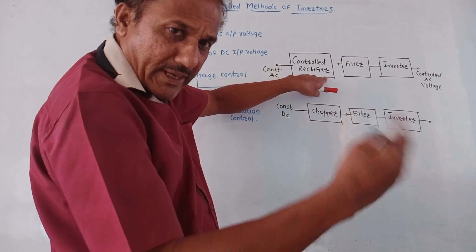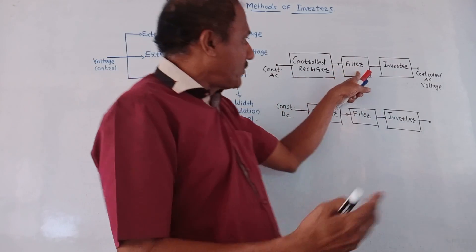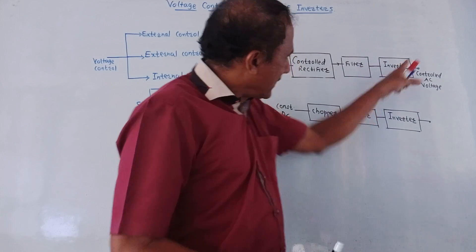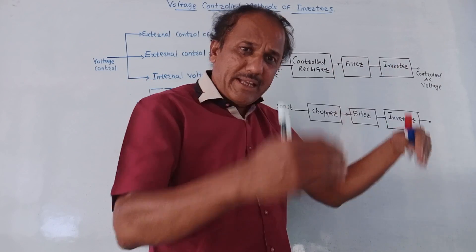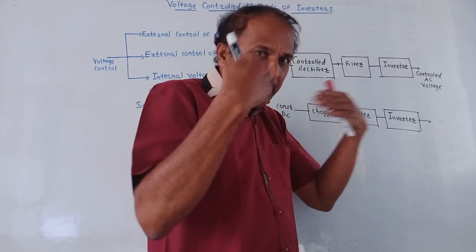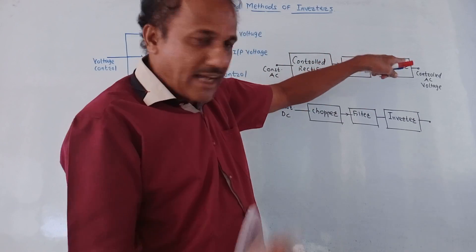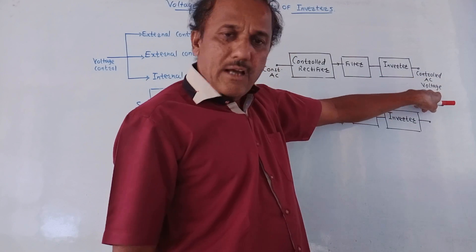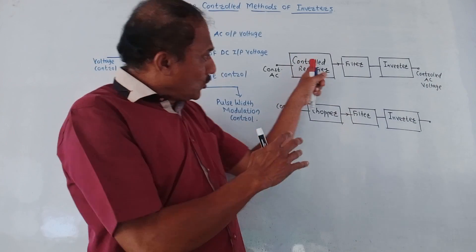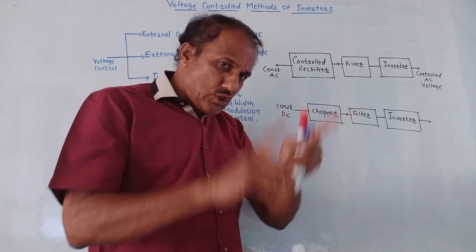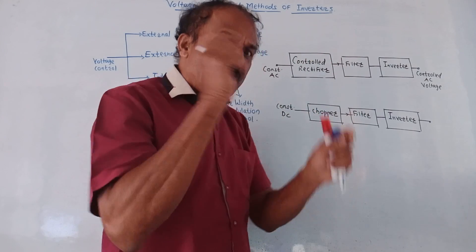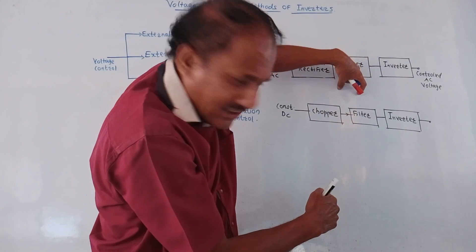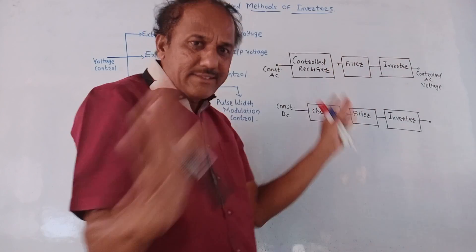The output of this controlled rectifier, which is a variable DC output, is applied to a filter to remove ripple, and then this is applied at the input of the inverter. So at the input of the inverter we are getting variable DC, which we can adjust as per the requirement, and at the output of the inverter we are getting controlled AC output voltage. If you don't want to use a controlled rectifier, another option is to use an uncontrolled rectifier with a chopper in series, then a filter, and then the inverter.